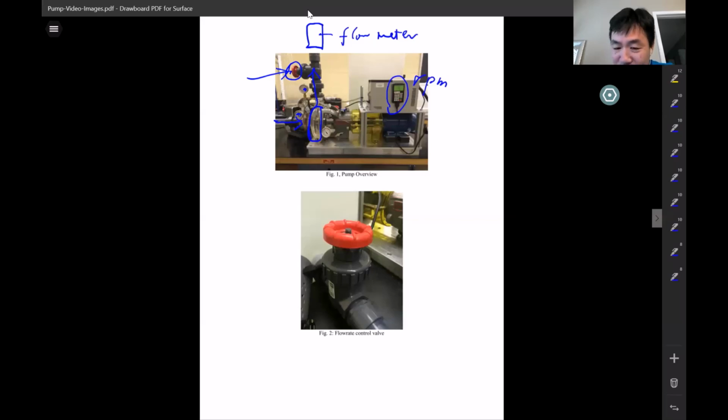In other words, you cannot say, hey, I set the first pump to 90% RPM, then go through 6 valve openings and measure the pump curve for the first pump, then set the second pump to 60% RPM and go through the valve openings again, 1, 2, 3, 4, 5, 6. You can produce the two system curves, but you lose the opportunity to compare the ratio, because every time you open, there's no mark on the valve, right? You have to set 6 different openings, six different times.